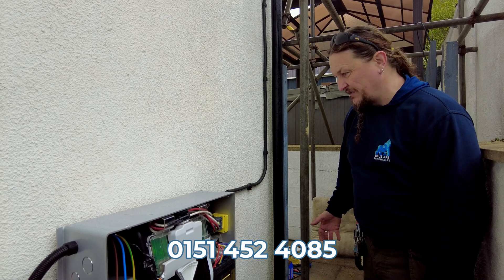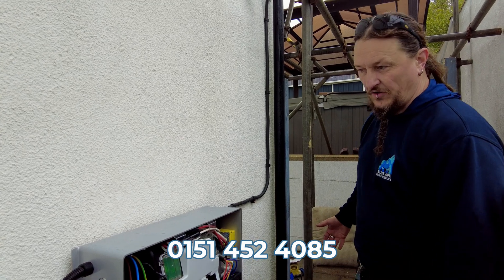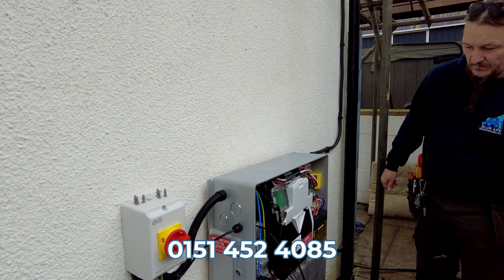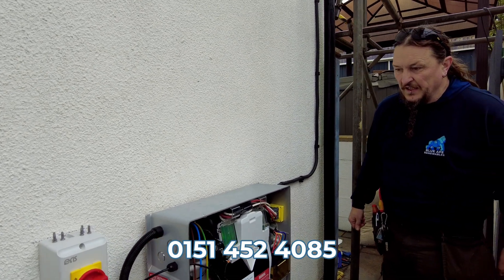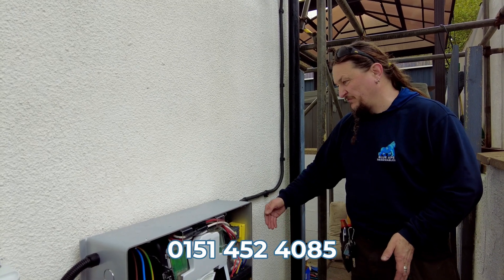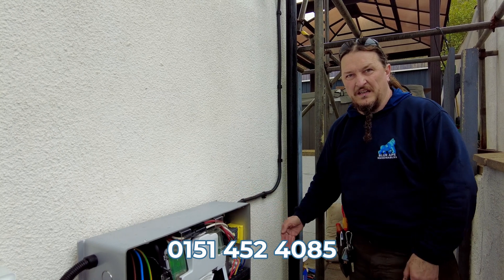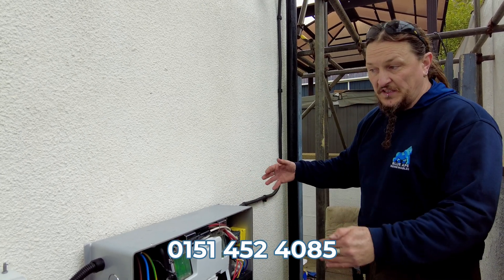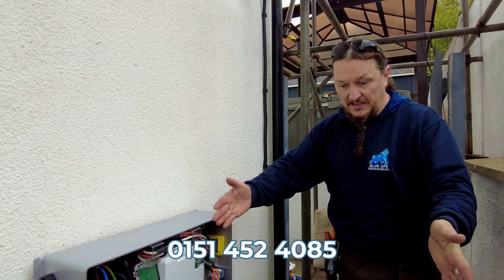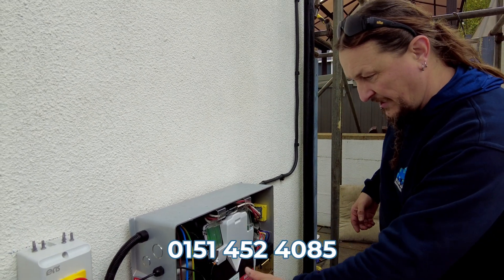With the wall anchors and the feet, it's not going to move anywhere. We can see that the cables are installed from the side, but obviously you can install it with rear entry. There's no particular reason for the side entry — honestly, just the layout of the building. The rear entry would have moved the unit slightly forwards, which wouldn't benefit in this case. The rear entry can be used if you've got expansion packs, as they can stack behind and on top of each other.